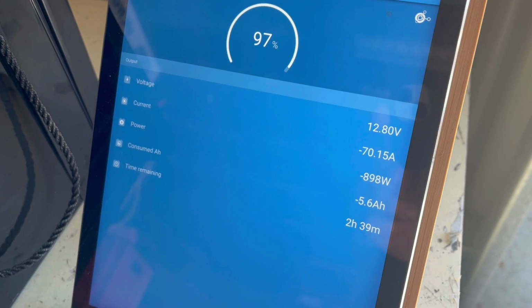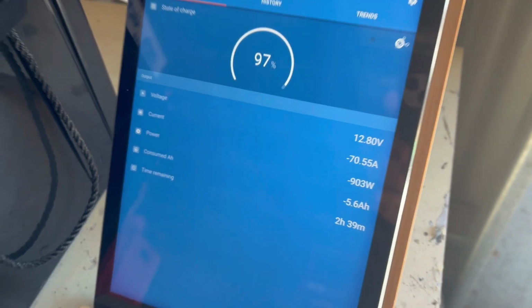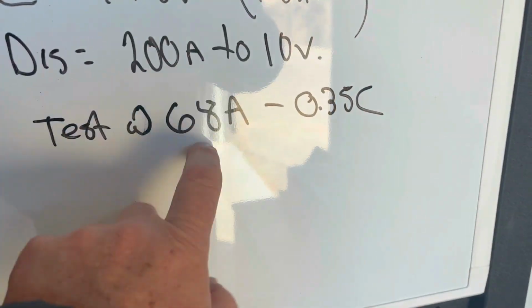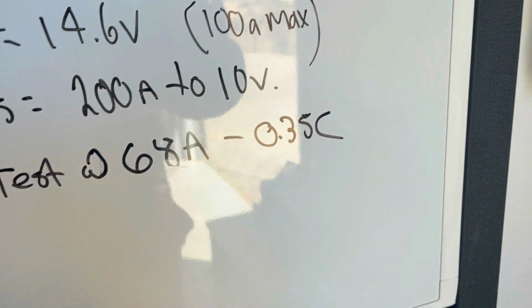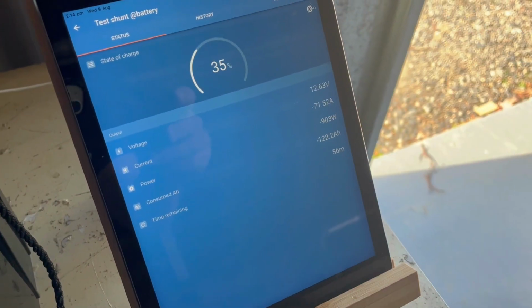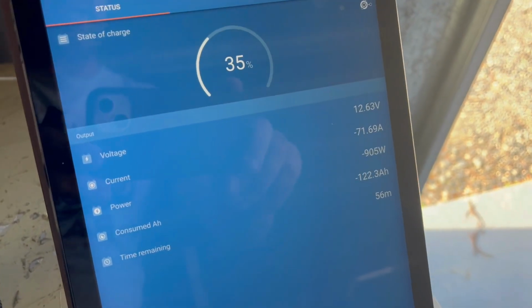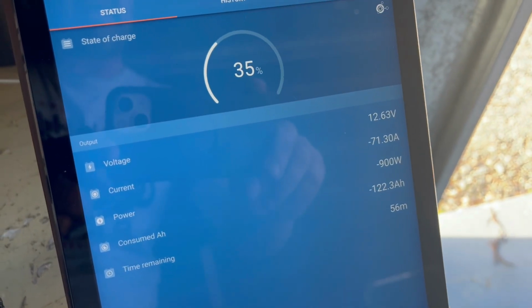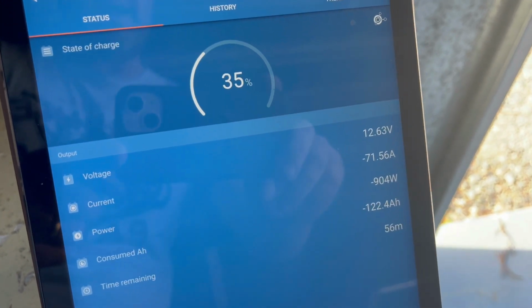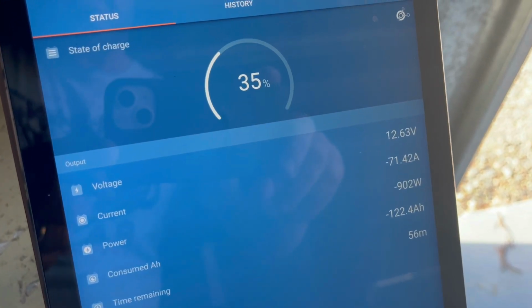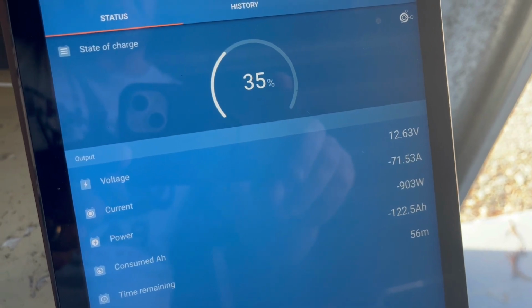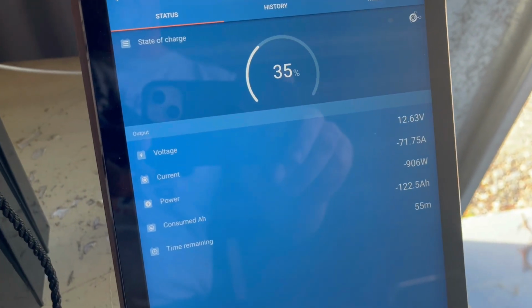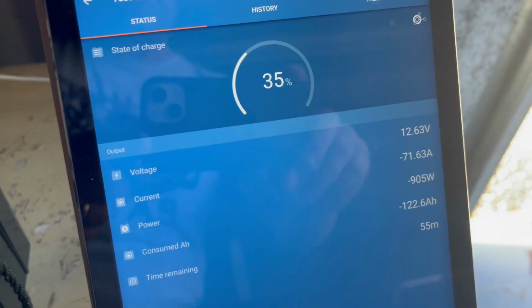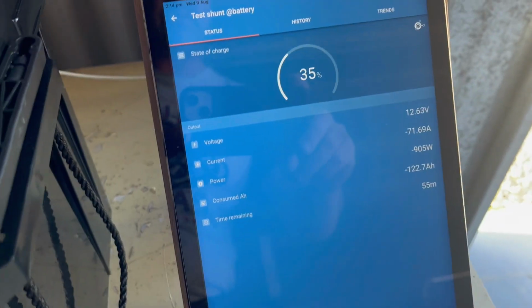Okay, it's settled in now at about 900 watts or 70 amps, which is around 0.35C discharge, so obviously that's a lot. It's been running for some time now. We've taken 122.3 amp hours out of the battery, still running around that 900 watts. Let's have a look, 71 amps, which is what I said before, so it's come down a little bit. 35% capacity remaining, so we'll come back a bit later and see how we're going.